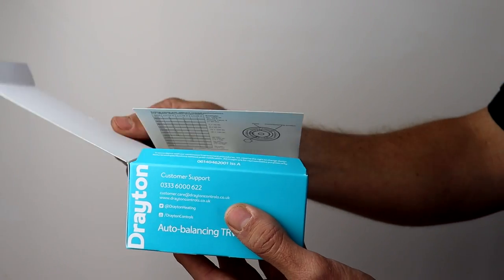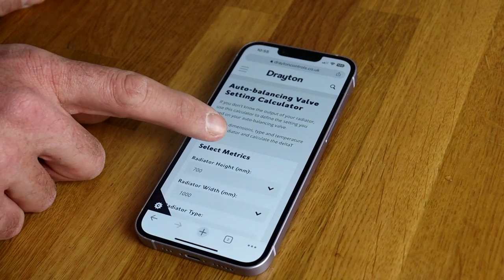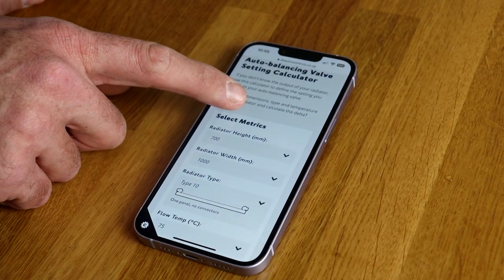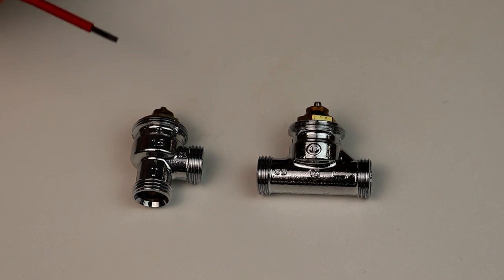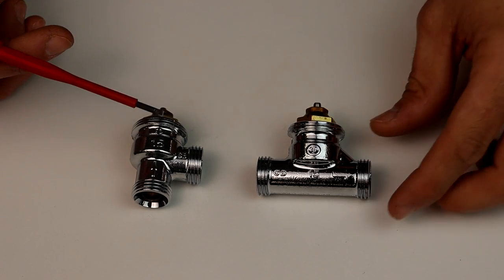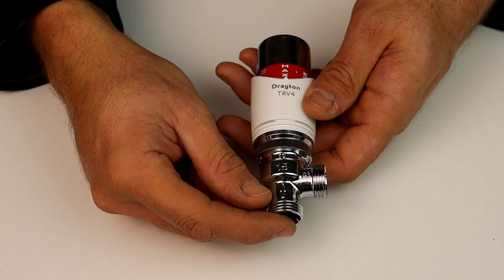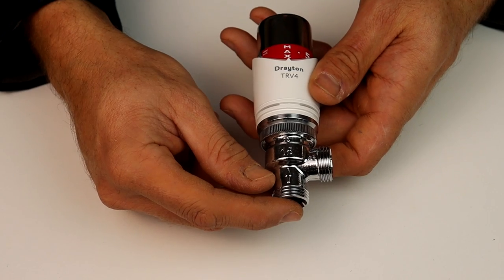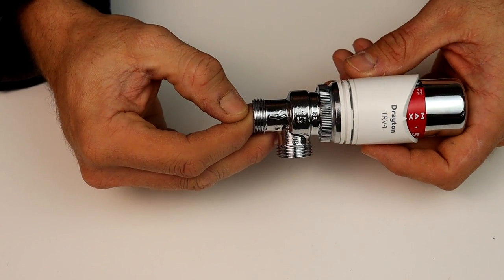This can be established from the data on the box if the radiator output is known, or for retrofitting we have an online calculator which uses the radiator size and type to identify the flow rate. These valve bodies are unidirectional, so you need to observe and follow the flow direction arrow when fitting. They can be fitted on either the flow or return. However, if the angled body is fitted on the return side, the sensing head will need to sit horizontally to respect the flow direction.